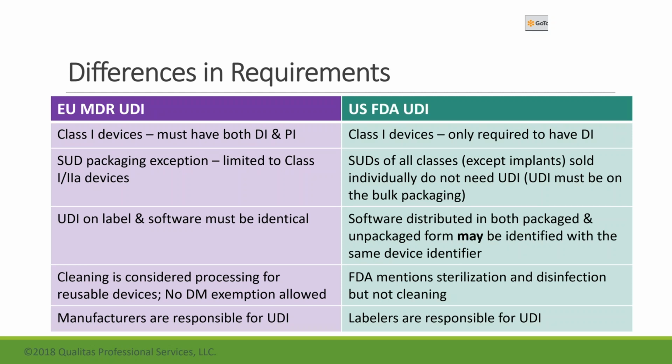In the EU, again, the UDI on the label and the software itself must be identical, but in the US it may be identified with the same device identifier or a different one. In the EU MDR, cleaning is considered processing for reusable devices. Okay, so that's important to know because the FDA mentions sterilization and disinfection, but not cleaning.